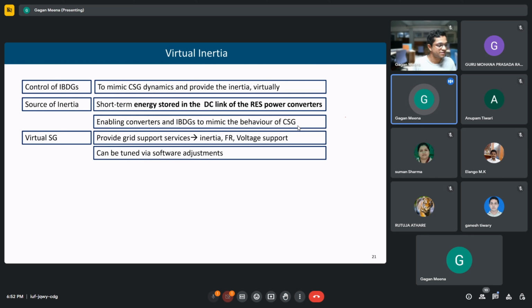But that is not possible for these inverter based DGs. So the virtual inertia concept is to mimic the conventional synchronous generator dynamics. The way they provide synchronous inertia, we want these inverter based DGs to provide inertia too. They cannot provide it in the same way, but we modify the control of these DGs so that they can provide a virtual inertia.